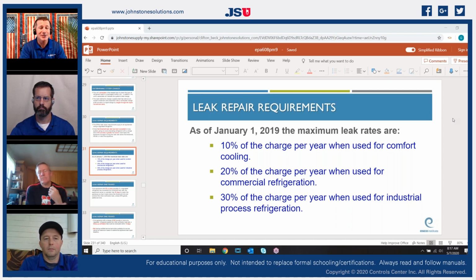So that is actually one of the reasons that you're starting to see new technology coming into equipment that will actually record. So like if you talk about some of the new refrigerant scales and refrigerant recovery equipment, they are actually Bluetooth connecting with your mobile devices like Service Titan and Measure Quick and some of these other electronic medias, so that can all be digitally stored. Johnstone has actually been working with CPS to implement a refrigerant scale that will automatically record your refrigerant charges off from your scales into your service documentation for you. So you have an electronic file of that. So it can be done either way. It can be done by the service contractor, but inevitably it is the responsibility of that building owner.